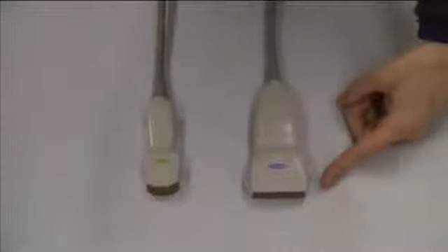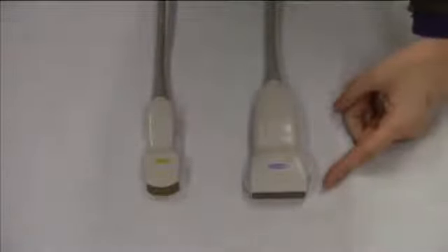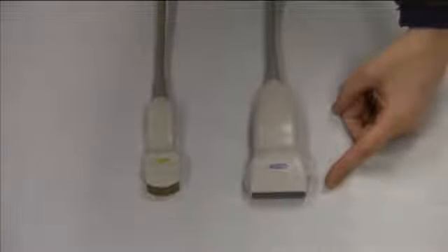In general, linear transducers are better for scanning superficial structures. They have better resolution of superficial things. When you scan your wrist to search for your radial artery, you will use this linear transducer. Curved transducers are typically better for deep structures. They have better deep penetration resolution. When you scan the abdominal phantom, for this demonstration, use this transducer.